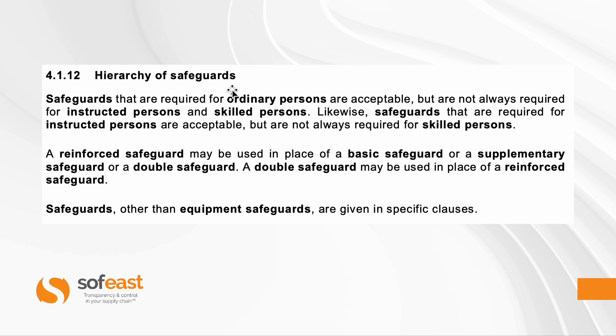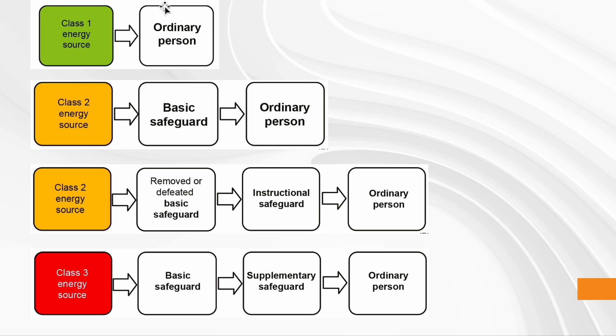For ordinary persons, certain safeguards are required. For instructed persons, typically fewer or weaker safeguards are acceptable. For skilled persons, even fewer. I'll focus on the ordinary person case. If it's a Class 1 energy source — not going to hurt anyone, not going to damage equipment — you actually don't need a safeguard.